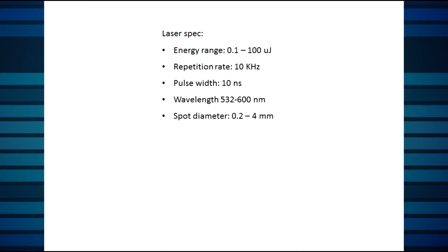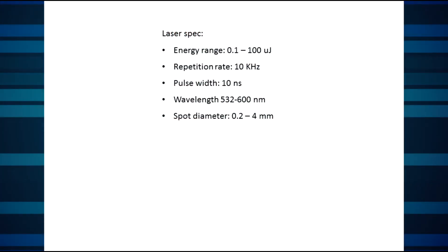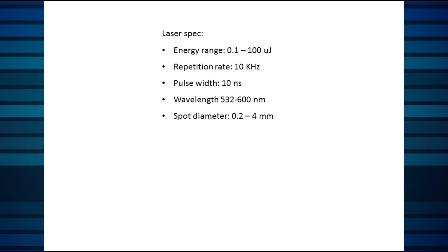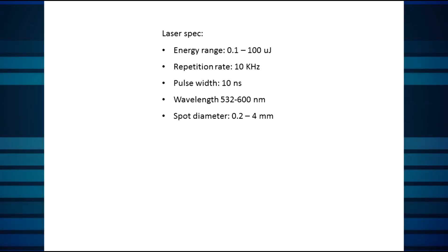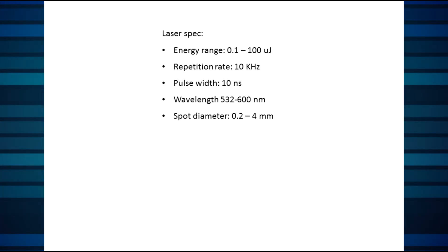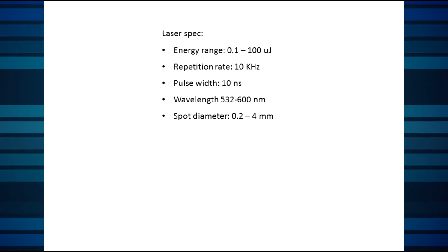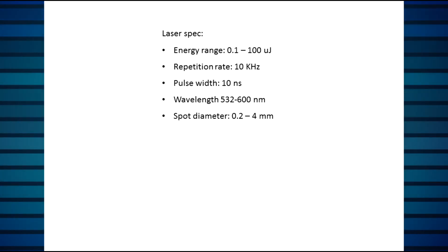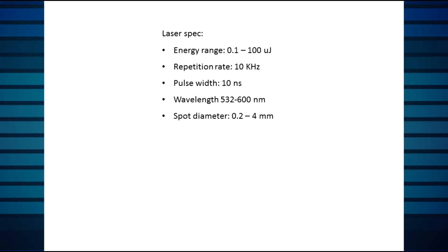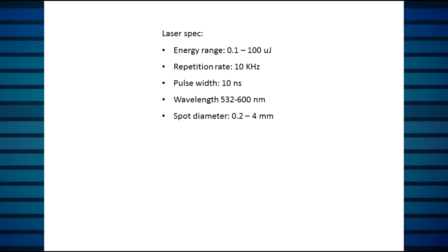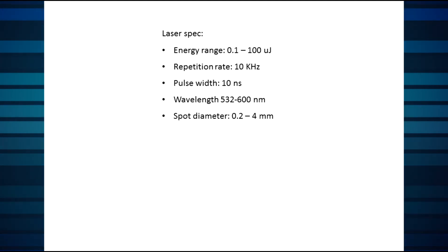Let's consider a detailed example from an actual recent inquiry for an energy sensor and walk through the thought process. Here are the laser specs: 0.1 to 100 microjoules, 10 kHz pulse rate, 10 ns pulse width, 532 to 600 nm wavelength, and 0.2 to 4 mm spot size.